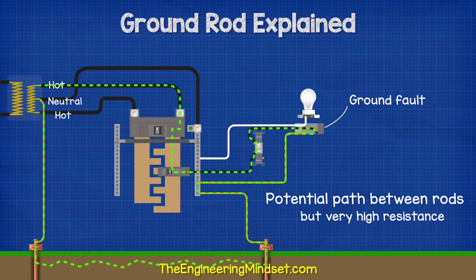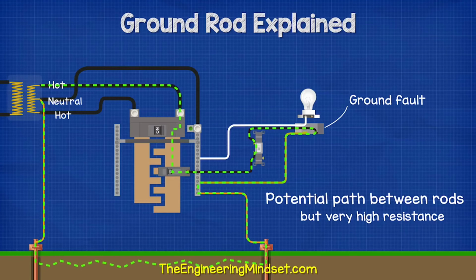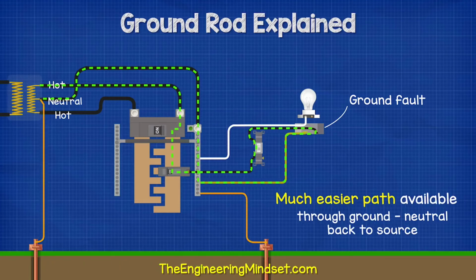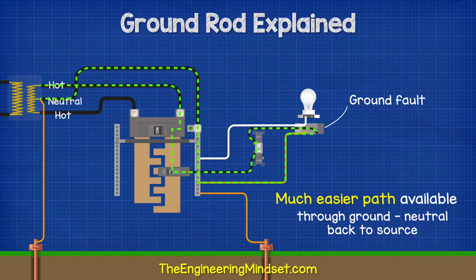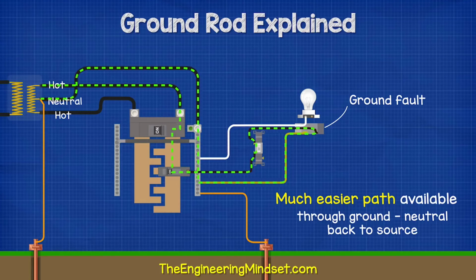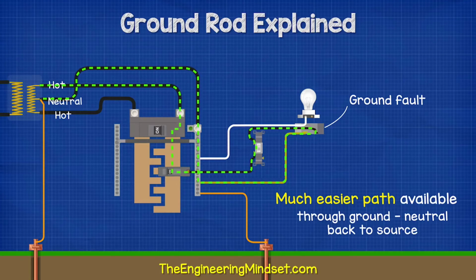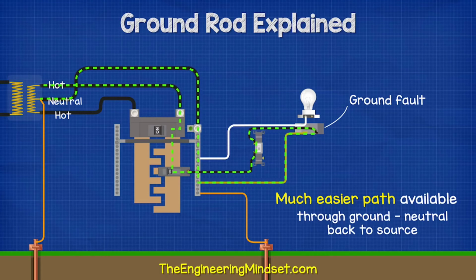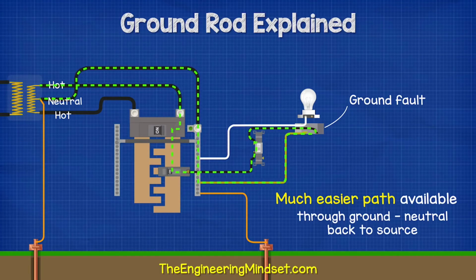But this path will have a very high resistance or impedance, and as we know, electricity will take preference over the path with the least resistance. So since we already have a very low resistance ground wire providing a direct path back to the source, the ground fault is going to take this route instead.